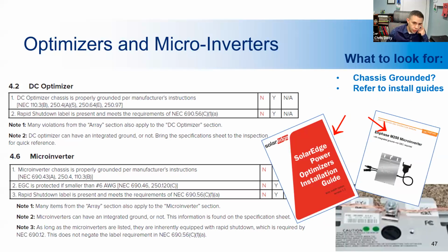More on the microinverters and optimizers: an important element of installing and inspecting this type of equipment is a thorough understanding of the instruction manual, as you can see examples here, which may include specific considerations for that device, such as mounting or bonding and grounding, as well as limitations on string configurations, etc. So you want to familiarize yourself with these so that you are aware of the limitations.